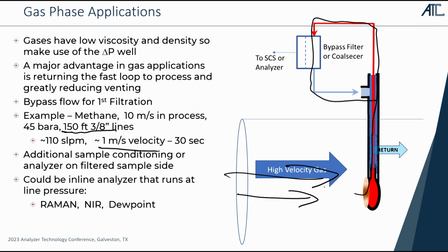This goes completely against everything I've ever taught all of you in a sample conditioning class, where I've said, if you've got a high pressure gas, the first thing you want to do is put a regulator in to lower the pressure. We're actually saying we're going to build this fast loop at high pressure. It goes completely against everything we talk about in our sample conditioning classes, where we say if you want fast response time, go with really narrow diameter tubing. This loop will run faster if I put larger diameter tubing in, because the tubing contributes less pressure drop then. But it allows me to create a fast loop that will continuously run and return to process.